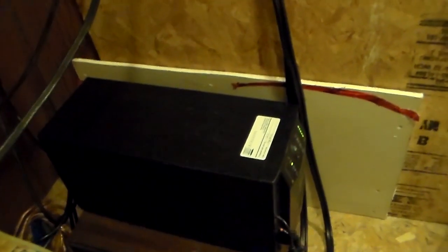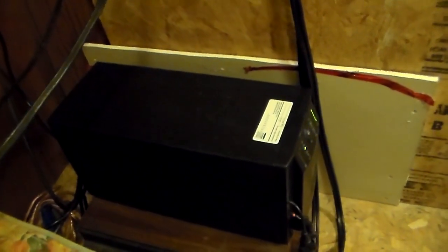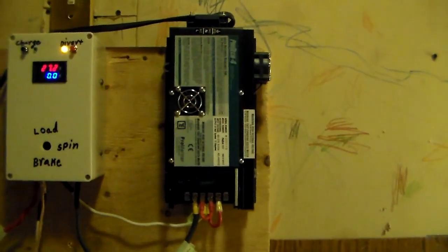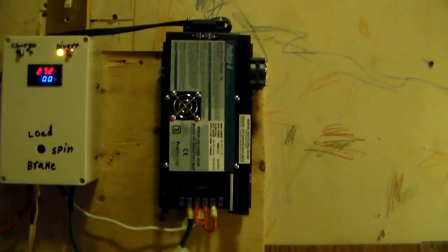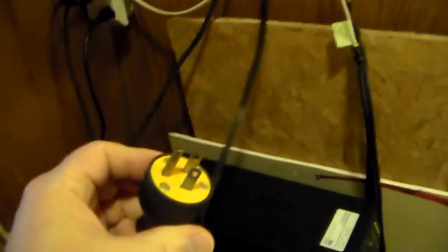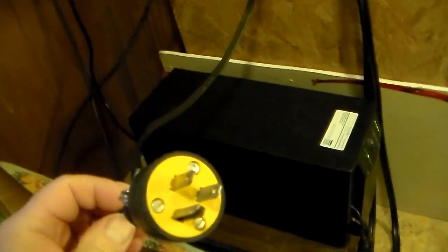So what you do is you basically create a double conversion UPS, which is one that runs completely on inverter and also runs on power provided for it from another AC source. So during a power outage that's extended, I can start my generator.